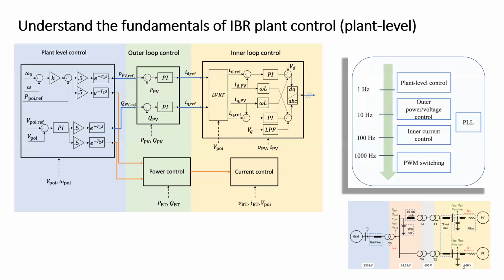Moving on, once we put IBR into the grid, you have to put in a lot of plant control, which has not been mentioned in the textbook yet. Here, we can see a hybrid power plant. It consists of one PV and one battery. At the plant level, there's a control which measures the frequency and sends out the real power order to both PV and battery. It also measures the voltage at the point of interconnection and sends out the reactive power order to both converters. So this is the hybrid power plant level.